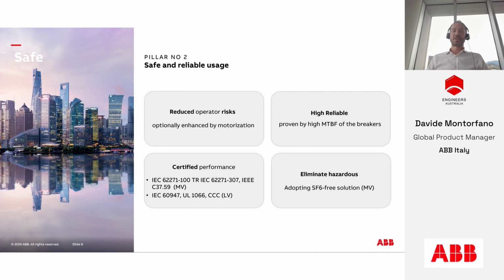Last point, of course, we want to eliminate hazards, both for technicians and for the environment. For instance, in medium voltage, we are now adopting vacuum technology, which for ABB is called VD4, a fully SF6-free solution. So we want to eliminate SF6 from the installation if it's required. Also, we eliminate outdated components that 40 years ago were possible to use but can be hazardous for the operator, like asbestos in some cases, or for the environment, like oil circuit breakers, taking the oil out of the breakers. Now I hand over again to Matteo.